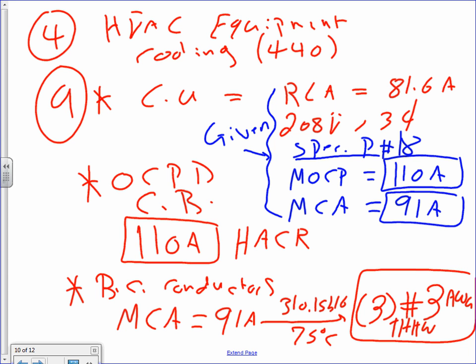So when we deal with HVAC equipment, the code says you have to use what's on the nameplate. Don't mess around with it. Okay, so sizing the overcurrent protection device. Do I have any option other than using 110? No, they're telling me 110. I'm plugging in 110. Branch circuit conductors, when I size the conductors, you size them based on minimum circuit ampacity, 91.